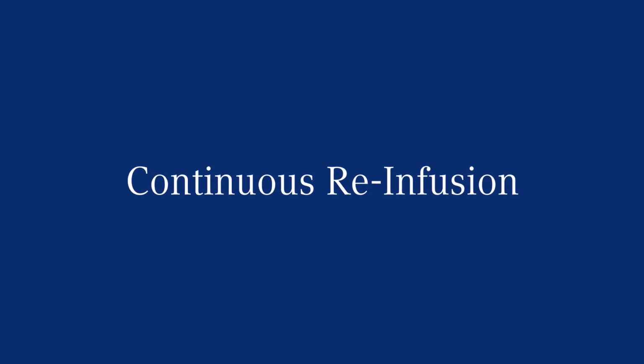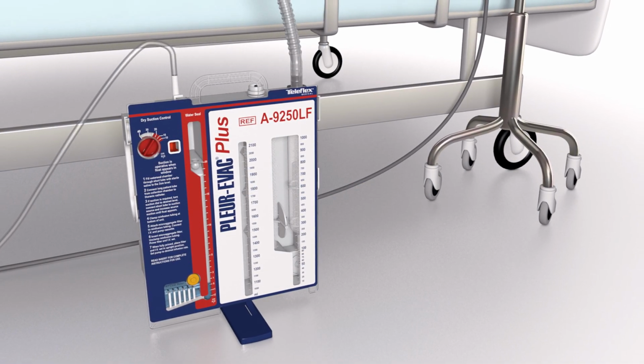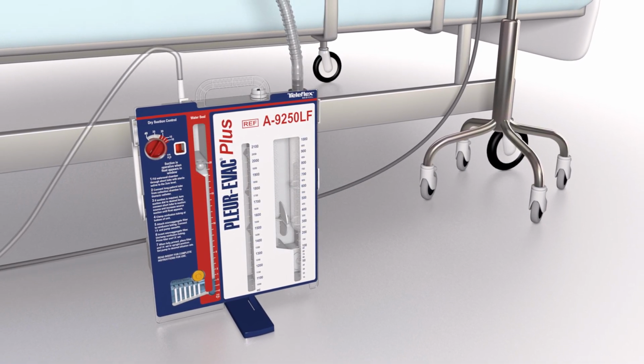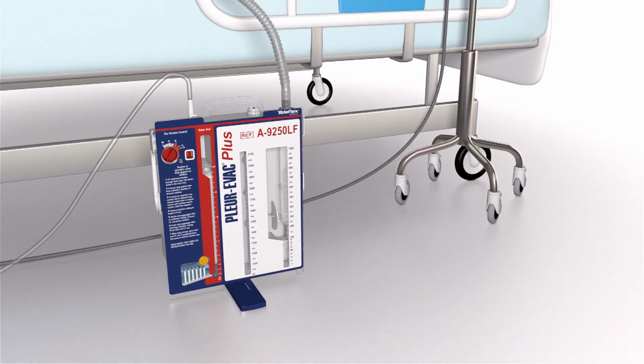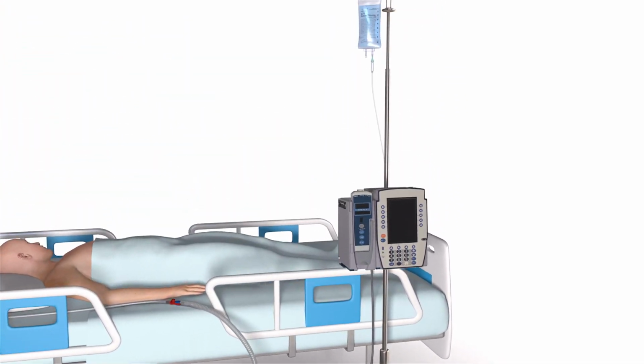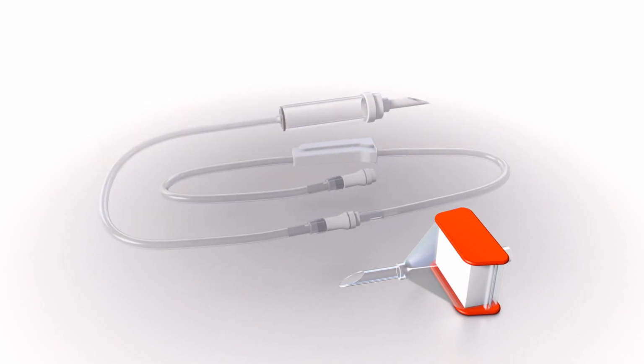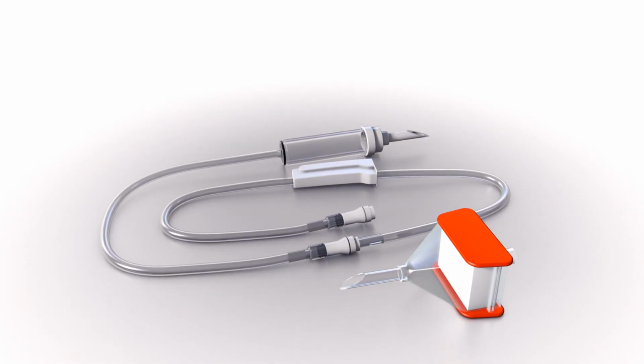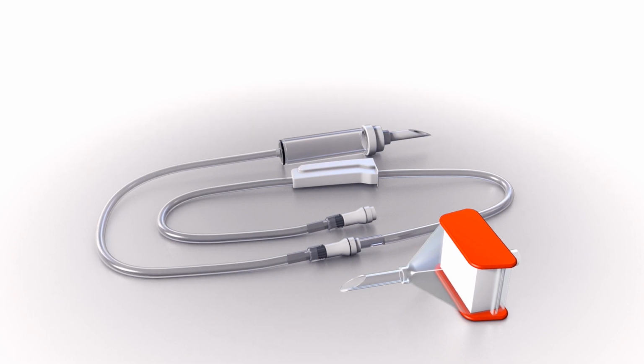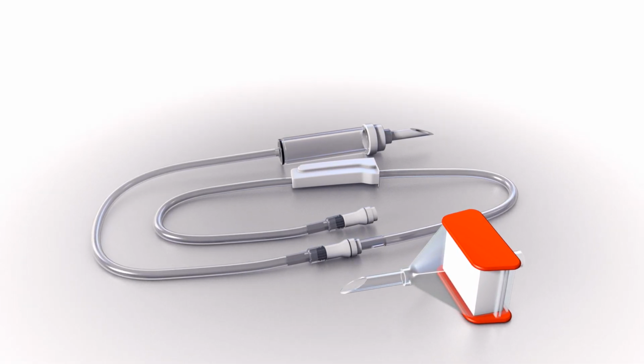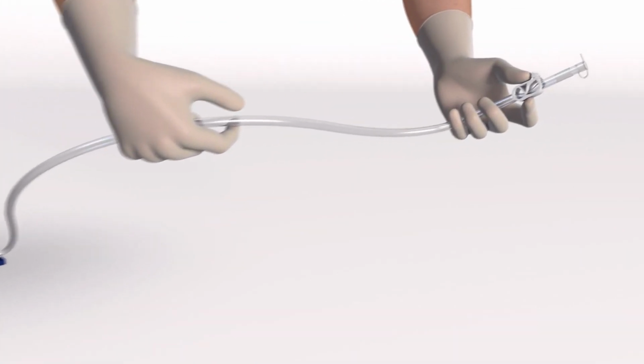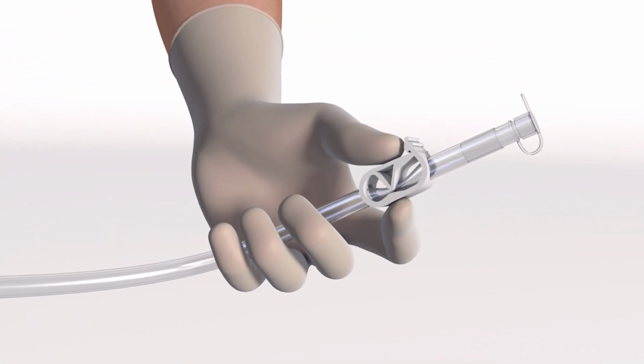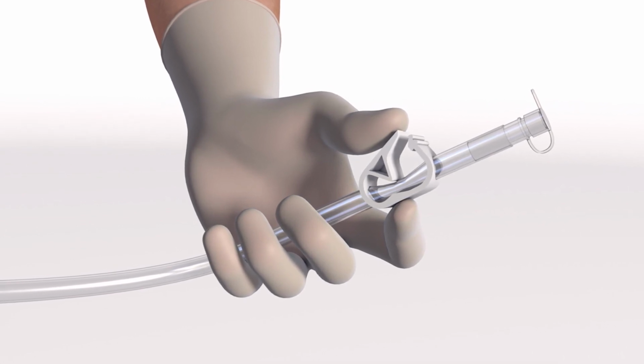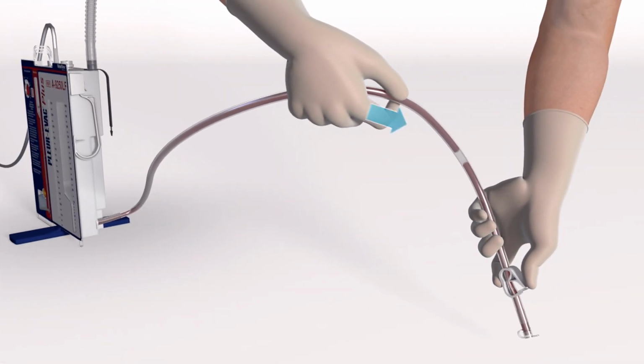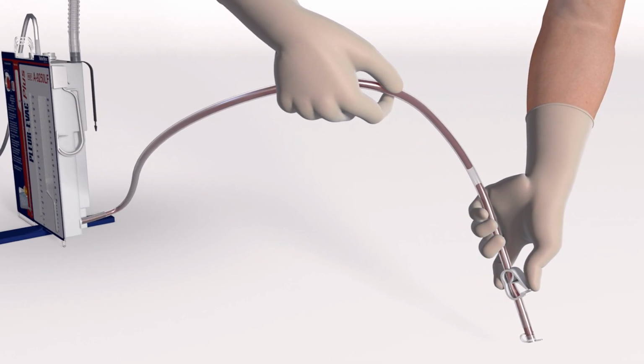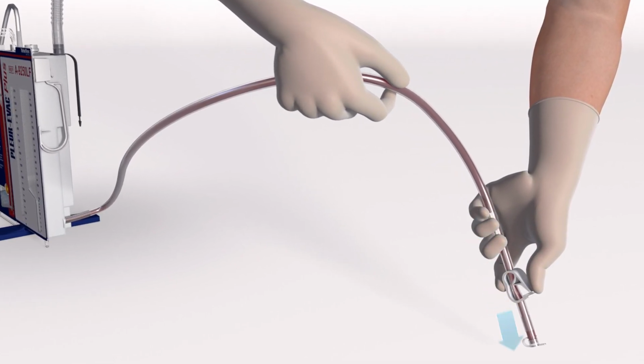To begin continuous reinfusion of autologous blood with the Pleur-evac A9250LF or S1150-08LF, start by setting up a blood-compatible IV pump. Obtain a microaggregate filter and an administration set for use with that pump. Prepare the reinfusion tubing for connection to the microaggregate filter and administration set. Be sure that the clamp on the Pleur-evac reinfusion tubing is open and the tethered exit port cap is closed. Hold the tubing below the bottom of the Pleur-evac device and gently milk it until it's filled with blood and free of air.